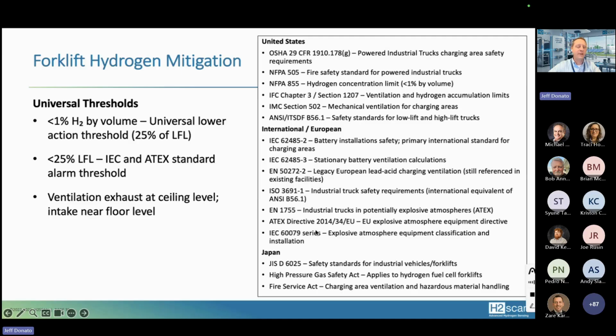The whole market is moving to 1% or below, which is why the HY-GUARD has a 1% relay. The first relay trips at 1% as its primary alarm, then has a critical alarm at 2%. This gives the operator on site a warning that the situation is getting worse, so they can take maximum action against what's going on.